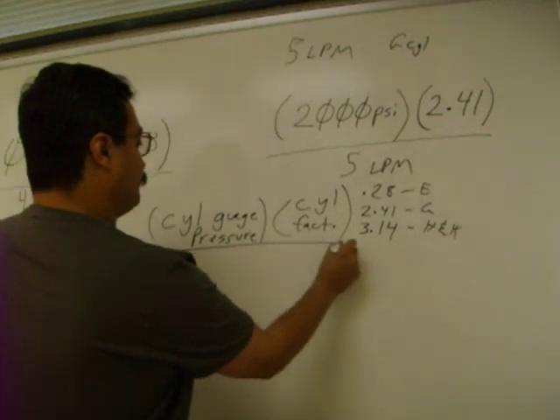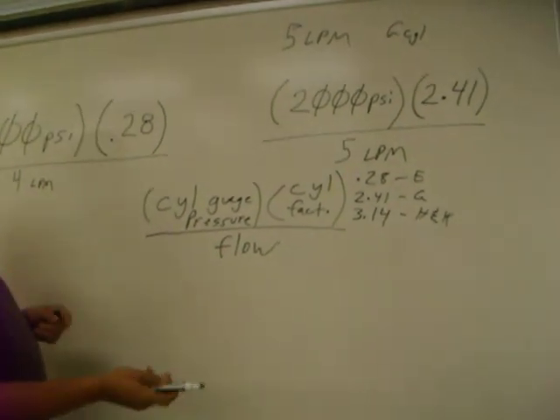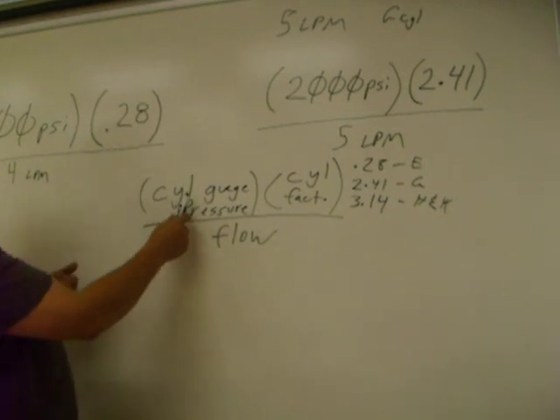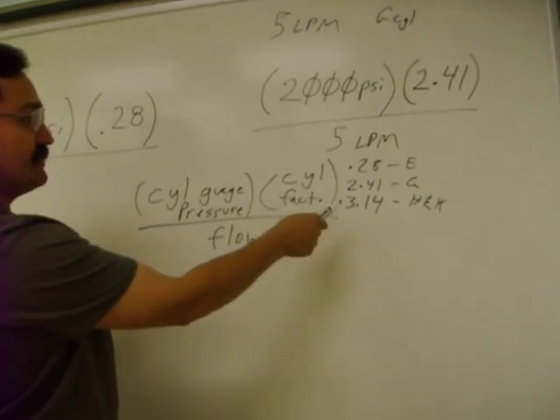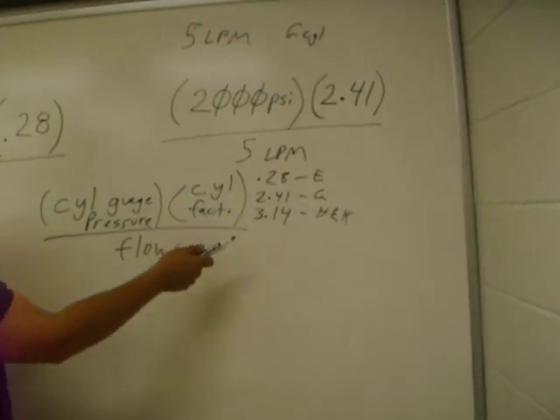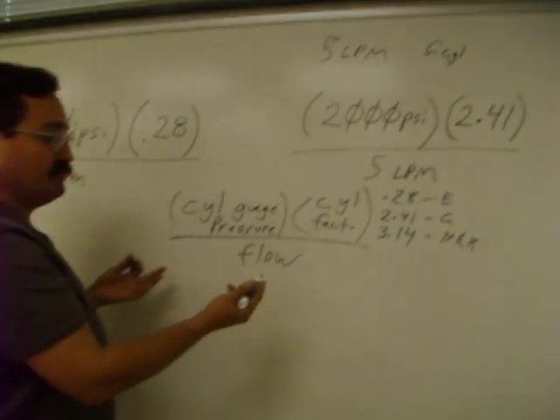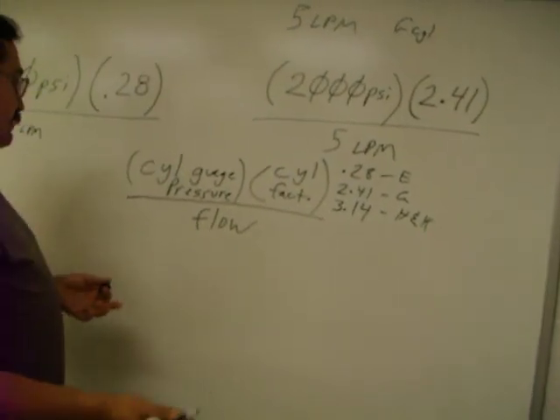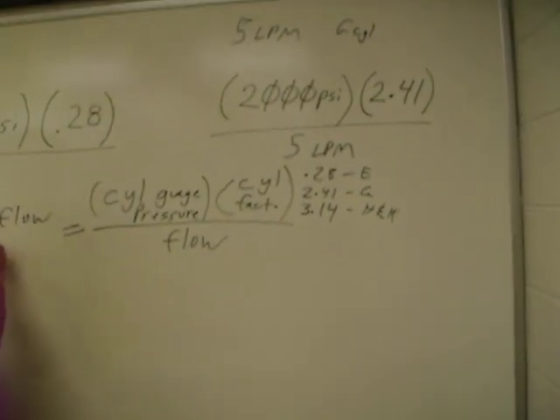The formula is cylinder pressure gauge reading, the cylinder factor, which each cylinder for different gases has a different factor. These factors are for oxygen and air. Then you divide it by your flow, which the doctor would prescribe as 2 to 10, or however many liters per minute. That's going to give you your flow duration.